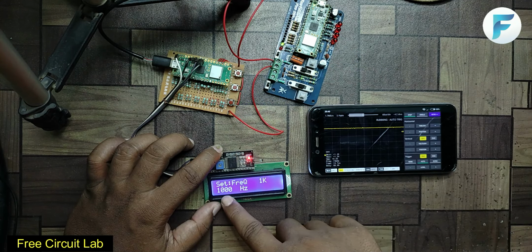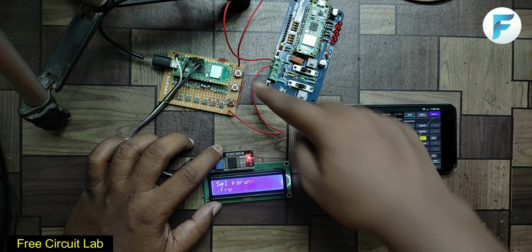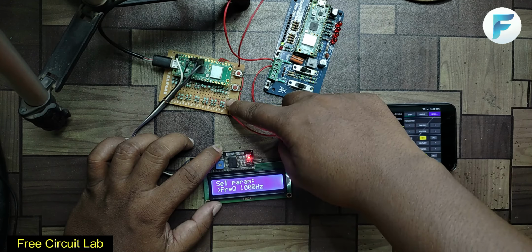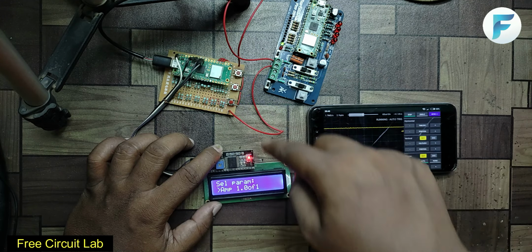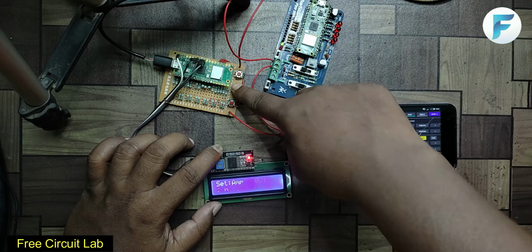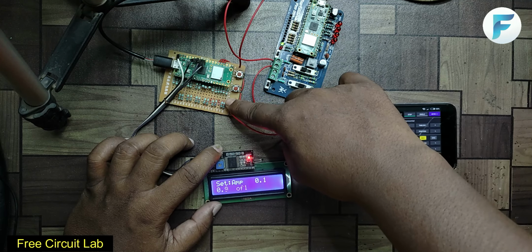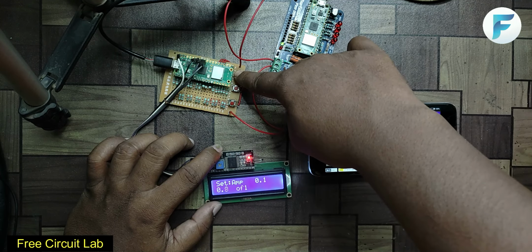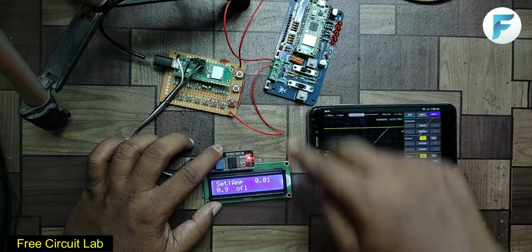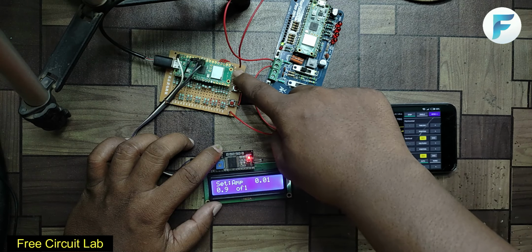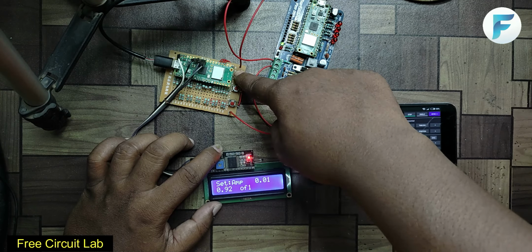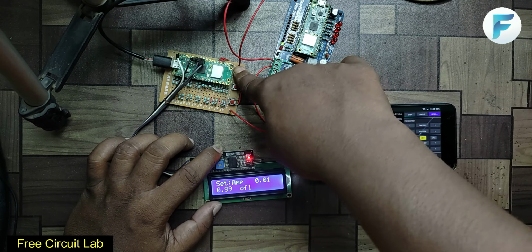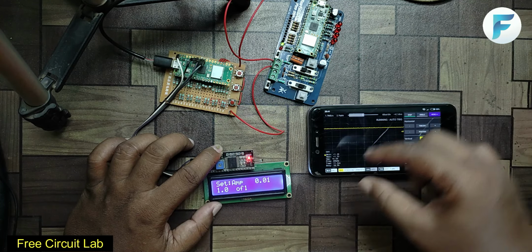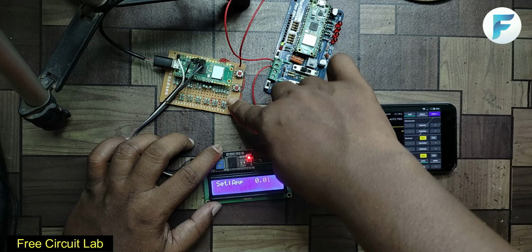Now it's 1 kHz. Clicking the middle button, frequency is selected. I can also change a couple of other parameters like amplitude. Select it, press decrement. It will lower the value by 0.1 each time. Again, same system. If I want to change the step size, press both together, then the step size will be 0.01 and then we can adjust it precisely.